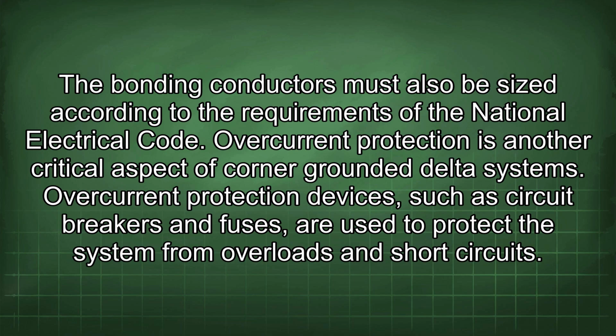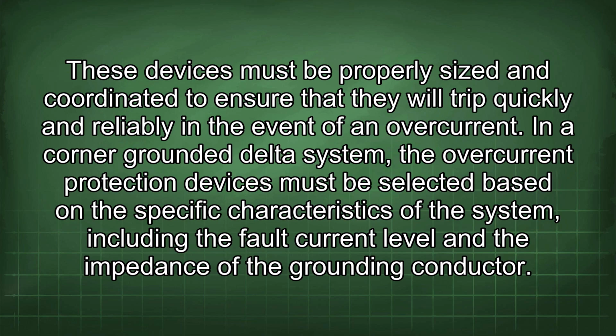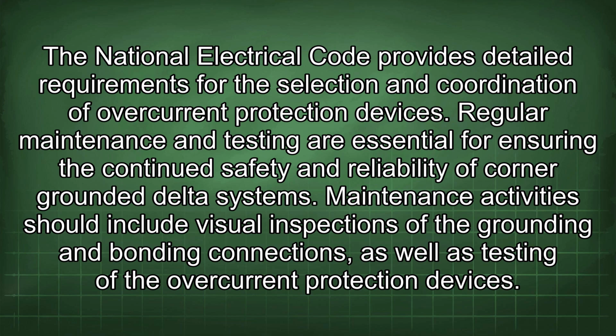Overcurrent protection is another critical aspect of corner-grounded delta systems. Overcurrent protection devices, such as circuit breakers and fuses, are used to protect the system from overloads and short circuits. These devices must be properly sized and coordinated to ensure that they will trip quickly and reliably in the event of an overcurrent. In a corner-grounded delta system, the overcurrent protection devices must be selected based on the specific characteristics of the system, including the fault current level and the impedance of the grounding conductor. The National Electrical Code provides detailed requirements for the selection and coordination of overcurrent protection devices.